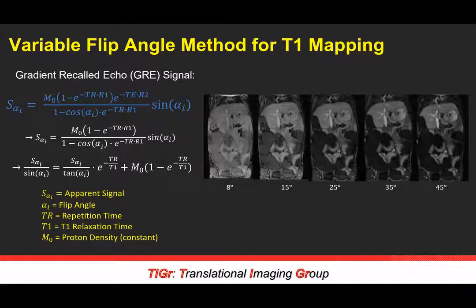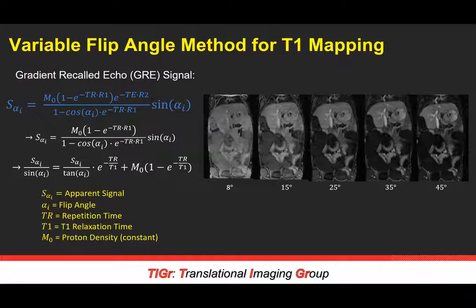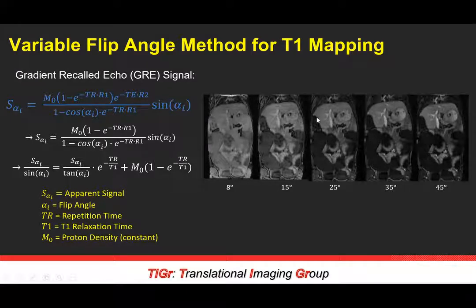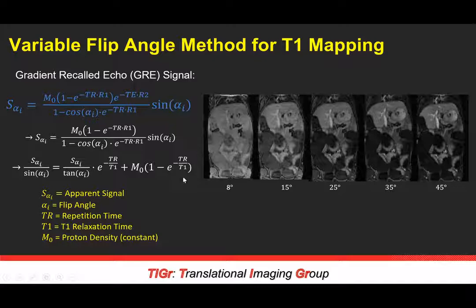How do we perform T1 mapping with this gradient recalled echo protocol? We require five different flip angles: 8, 15, 25, 35, and 45 degrees. You can see the impact on signal quality as the flip angle changes. We then take the GRE signal equation, reconfigure it to get a fit for apparent signal in the image, and relate that to known parameters such as repetition time and proton density. We then back-solve for the T1 relaxation time with knowledge of the flip angle.